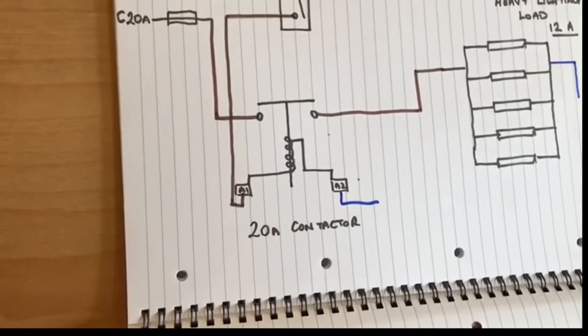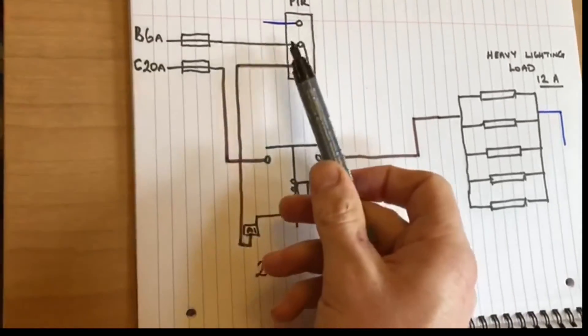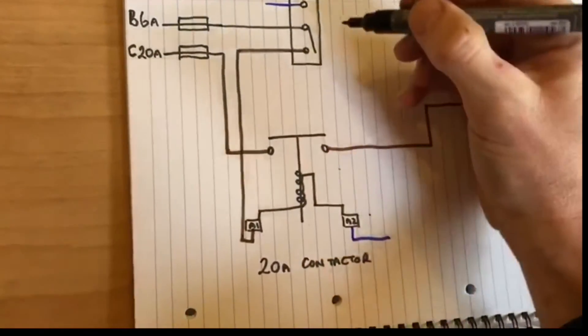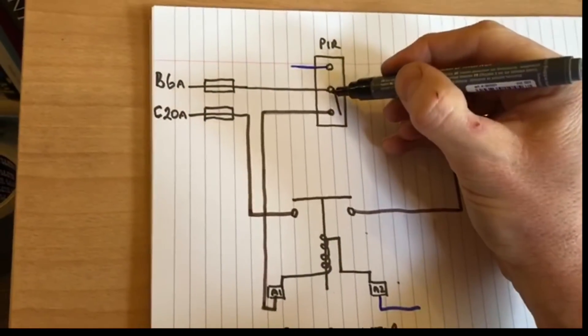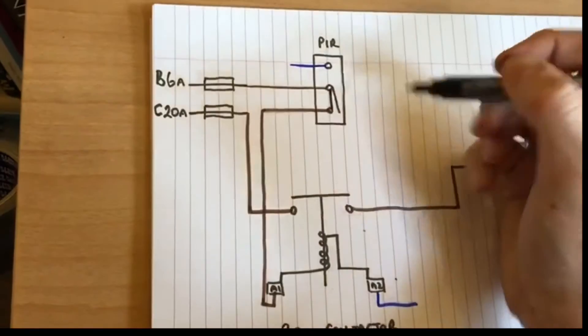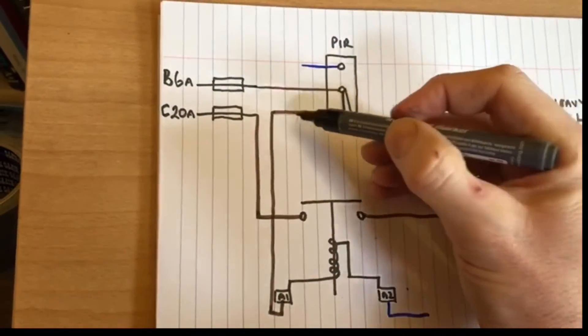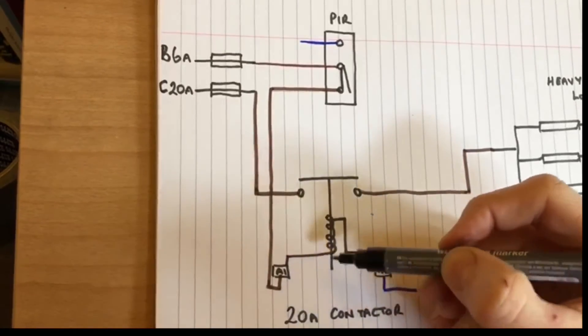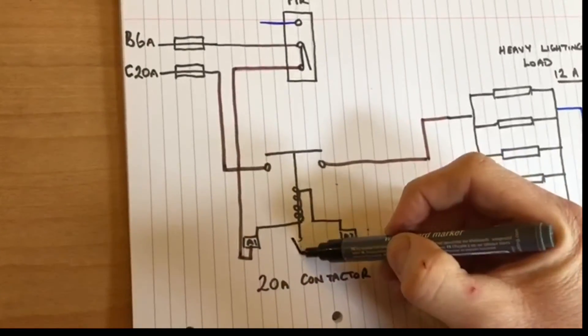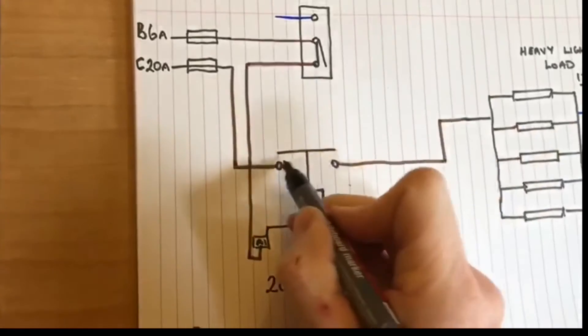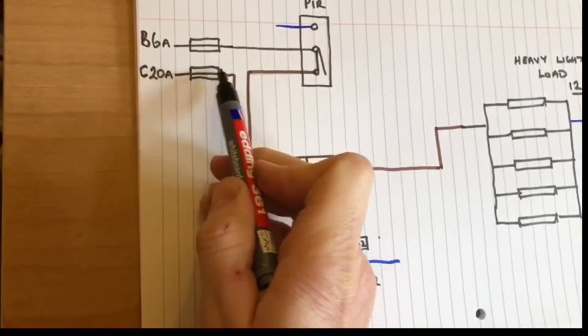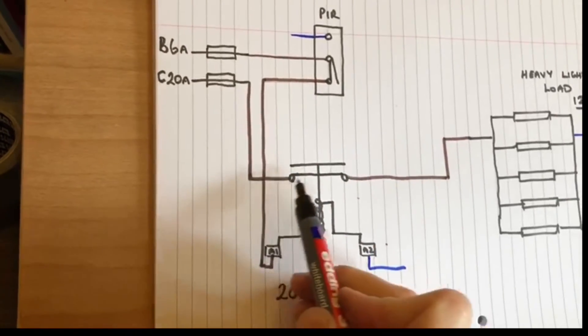So let's just talk through the operation of the circuit here. So again, we've got our permanent live feed here. So if someone is detected, or if this detects something, this will close. So the circuit now is going through to the coil, through to terminal A1. It pulls this down, it will make connection here, which then brings the full load coming through to the lights and the lights will illuminate.